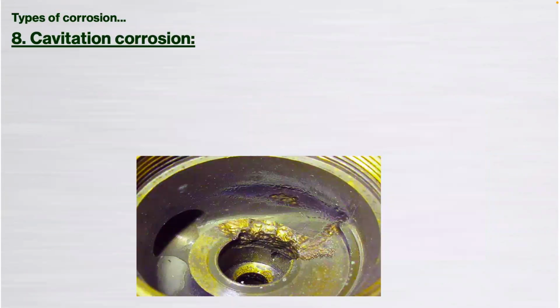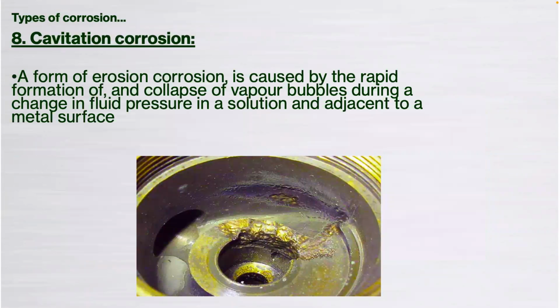And then there's cavitation, a bit of an anomaly. It's a form of erosion corrosion. So we have a formation and a collapse of vapor bubbles, and it's really during a change in the fluid pressure, typically adjacent to the surface. I'll give you some examples where you may see this. This particular picture is a control valve. You can hear this on pumps, in fact.